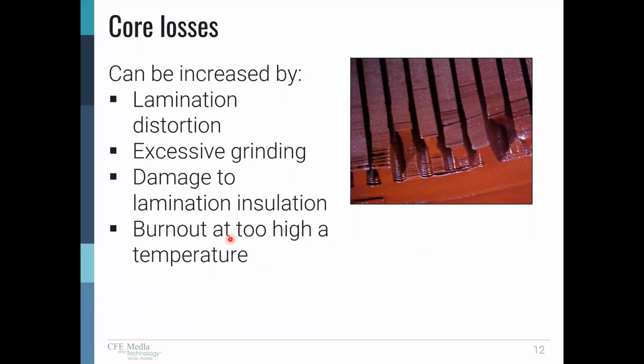Another way we have to be concerned in repair is that we process these in a burnout oven, and burnout is a misnomer. It's not burning the windings, it's heating the windings to a high temperature. We create thermal degradation. So these are the things that can affect the core losses in terms of what we're doing in the repair.